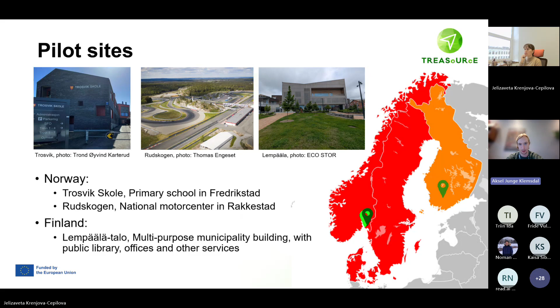At Trosvik Elementary School, they have 44 kilowatt solar panels on the roof, and we installed a battery system with 2 racks, giving 80 kilowatt-hour capacity and 40 kilowatt power capacity, running peak shaving and solar support. The battery room was built from scratch in an unused garage, requiring work to adapt the ventilation, electrical connections, and remote access through a 4G router.